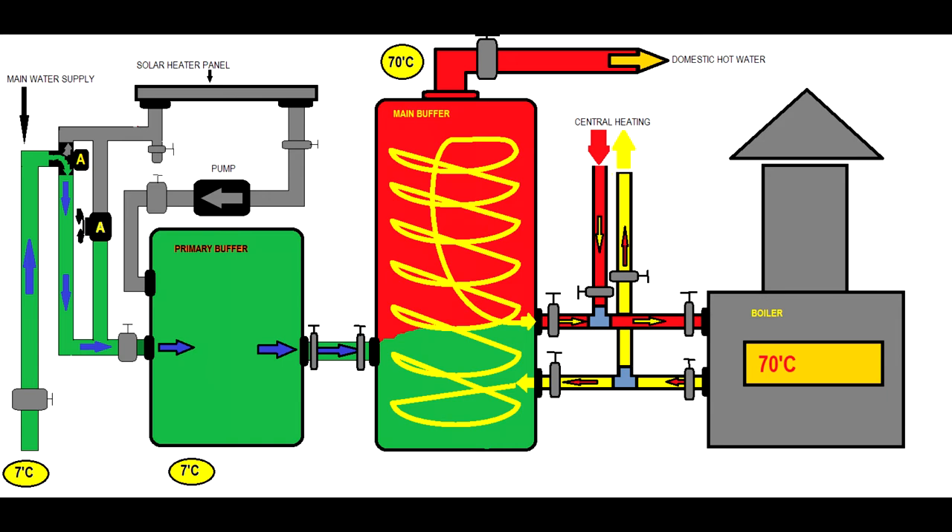You have to drain the solar heater panel in winter to make sure the water will not ice up and destroy your tubes — we all know that ice increases its volume. So the main water supply goes into the primary buffer and then to the main buffer. Unfortunately, in this case we will not save any energy because the main water keeps its low temperature all the way to the main buffer, and the boiler has to undertake 100% duty to heat the water — from 7 degrees to 70 degrees. There is nothing we can do to save energy in this case.